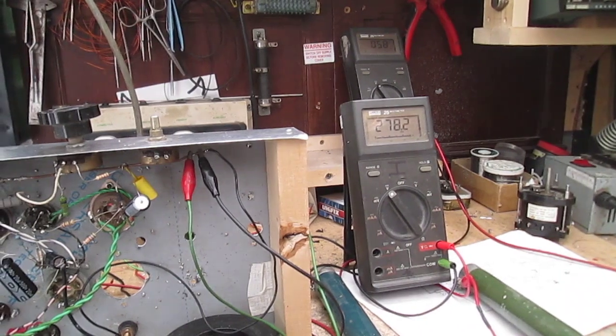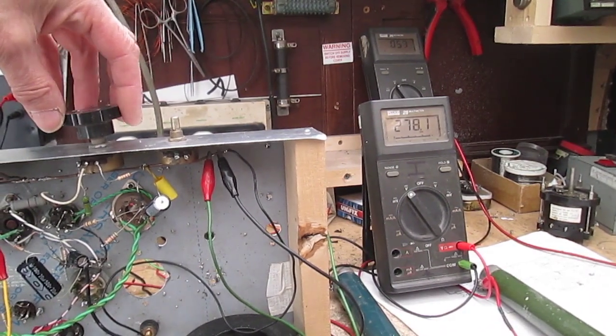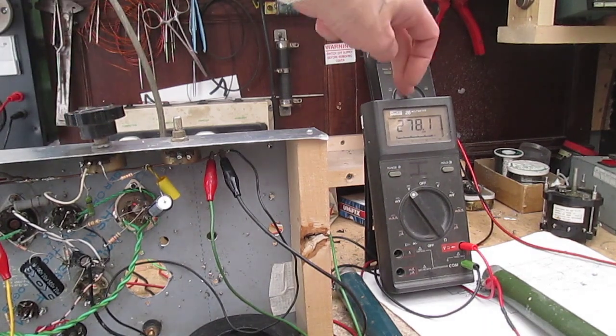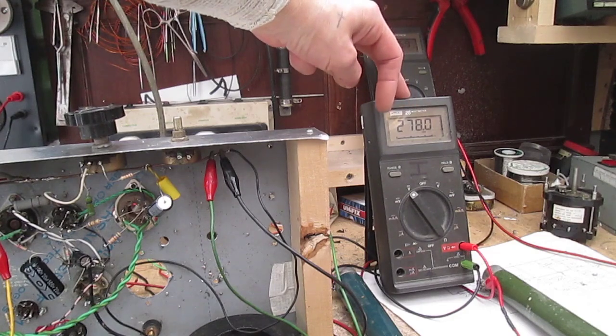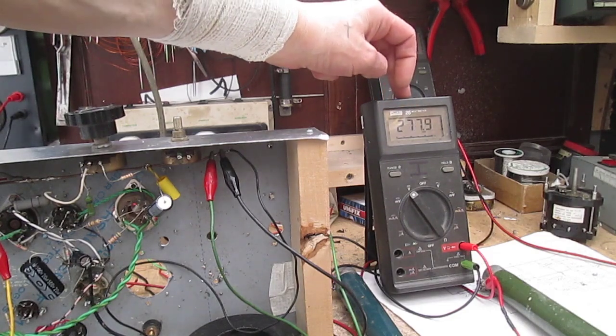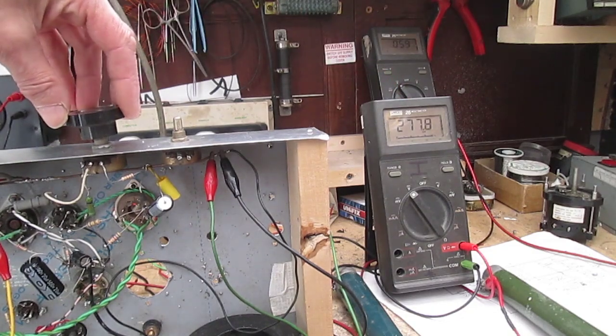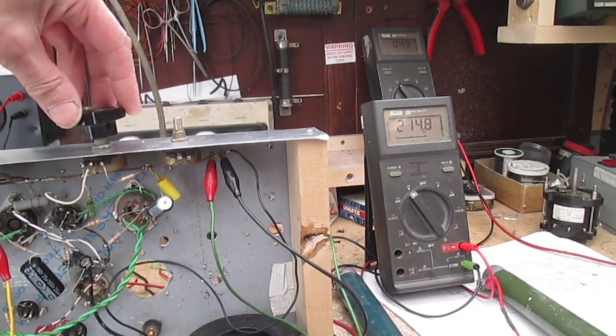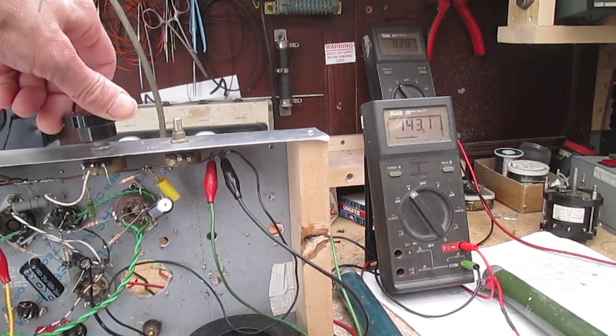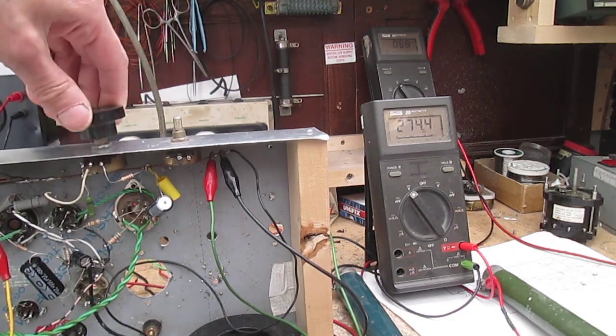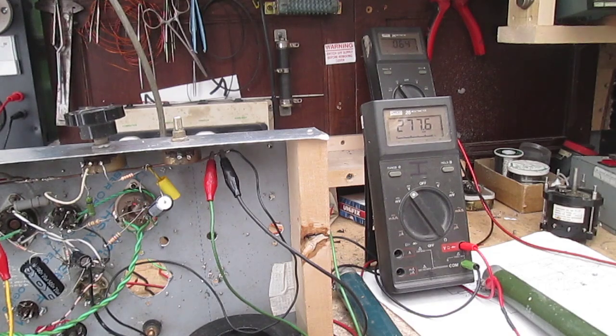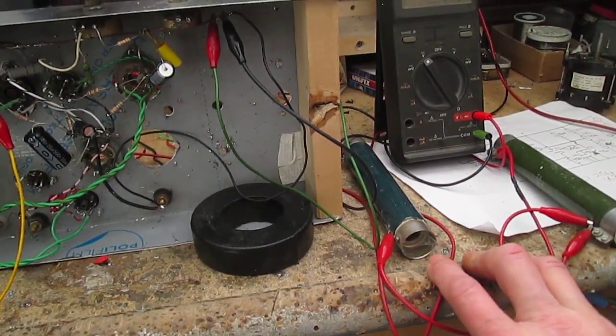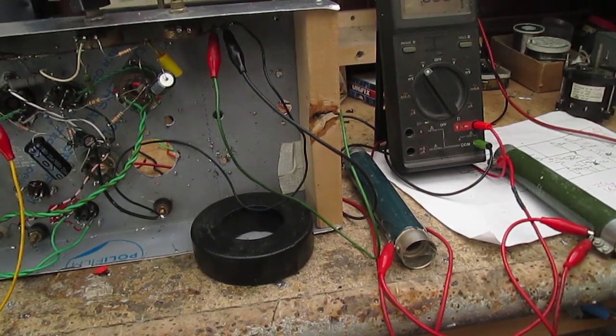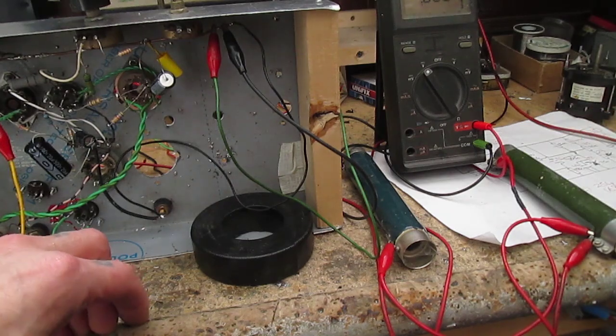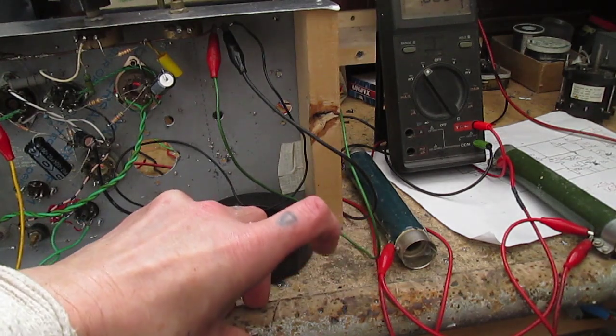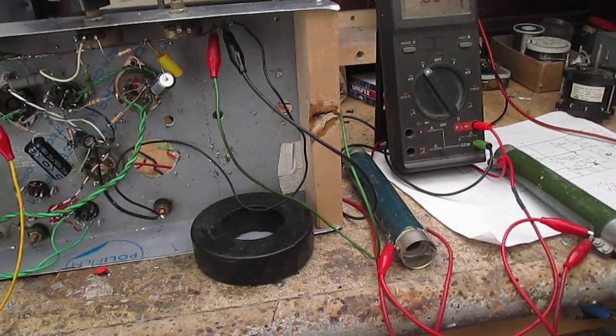Hopefully you can see everything at the same time. So we've got this potentiometer here that should adjust the voltage. As you can see, we've got about 280 volts, 350 going in, so we're dropping 70 volts across the series pass valve, which is not good. And I have an adjustment of about 150 volts to 280 volts. Earlier on I tested it with just the 2K power resistor, and with a voltage of 230 volts, 2K load, that equates to 100 milliamps high voltage current.